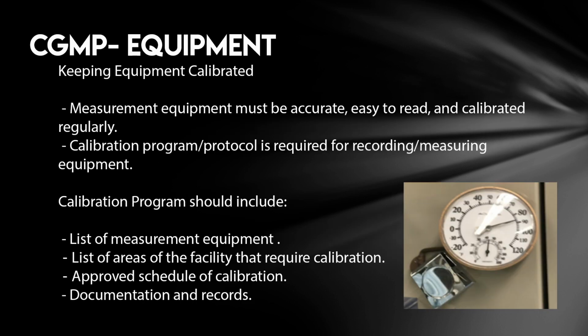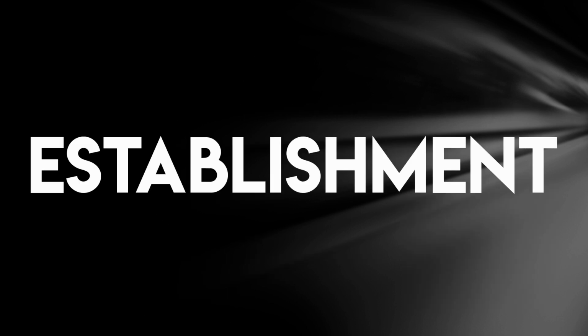When using measurement equipment, ensure it is calibrated to ensure accuracy and easy to read. Please also calibrate the equipment regularly. A calibration program or protocol is required for recording and measuring equipment. The calibration program should include a list of measurement equipment, a list of areas of the facility that require calibration, an approved schedule of calibration, documentation, and records.